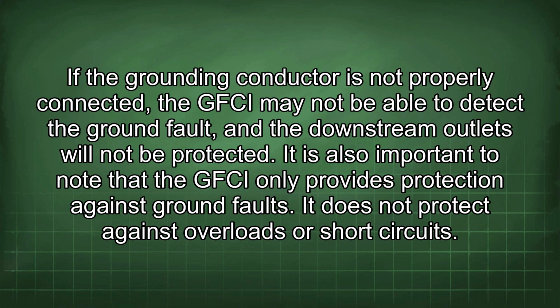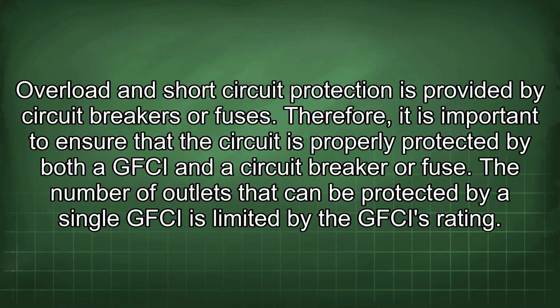It is also important to note that the GFCI only provides protection against ground faults. It does not protect against overloads or short circuits. Overload and short circuit protection is provided by circuit breakers or fuses. Therefore, it is important to ensure that the circuit is properly protected by both a GFCI and a circuit breaker or fuse. The number of outlets that can be protected by a single GFCI is limited by the GFCI's rating.